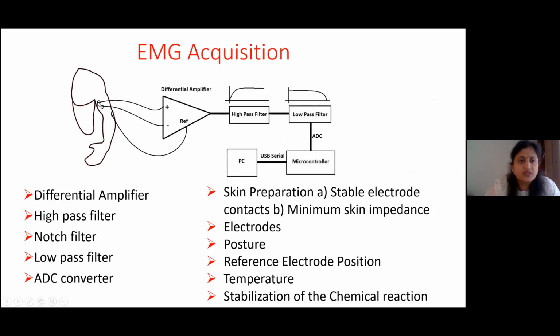First, this is a muscle. So this is the muscle signal. There will be one reference. Whenever acquiring the electromyographic signal, the placement of this reference electrode is very, very important. You have to identify a position where we have less muscle or zero muscle. We actually have a bone there, just inside your skin. At this position, you can place this reference electrode.